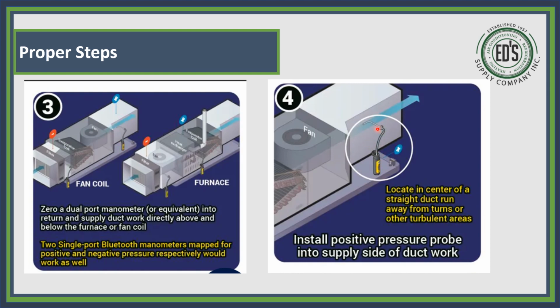So I want to go in here now. There's a couple of ways you can do this. I always like to go dead center of the ductwork because that's where my airflow is going to be, because air comes out of a fan in a circular motion. So if you're testing down here in the corners, you're going to get a false reading because you're not in the airstream or the jet stream of that blower motor. So I always try to get dead center of the ductwork.